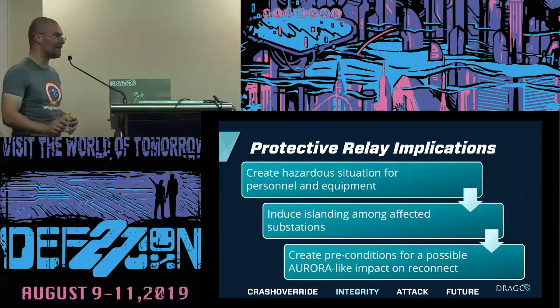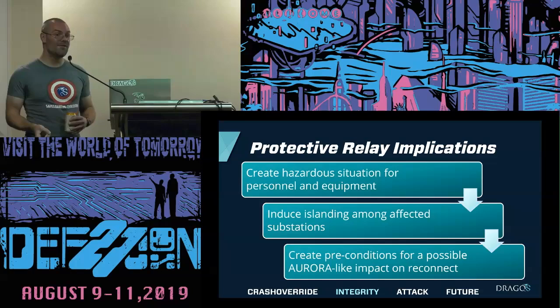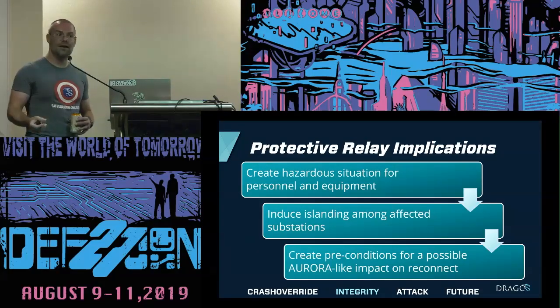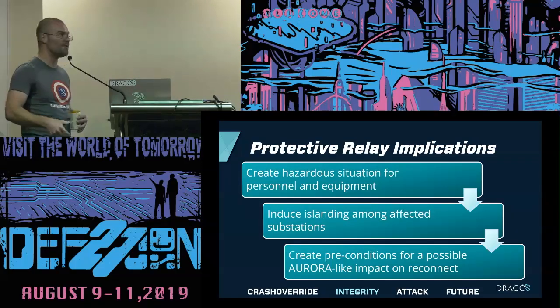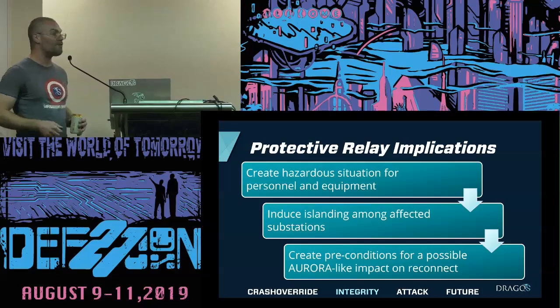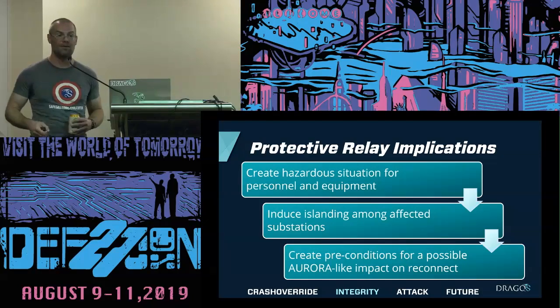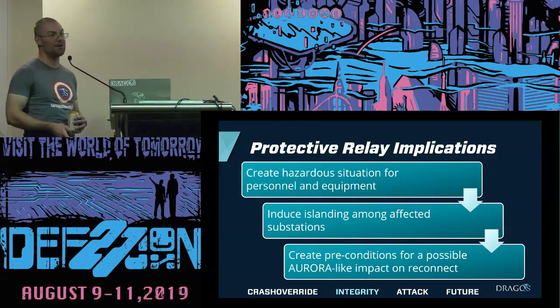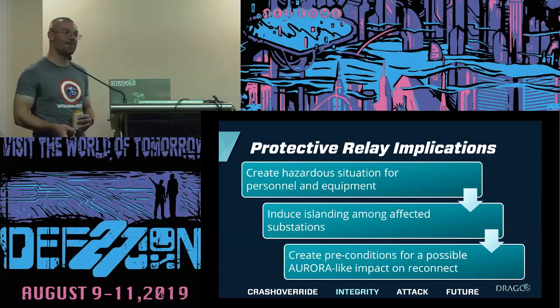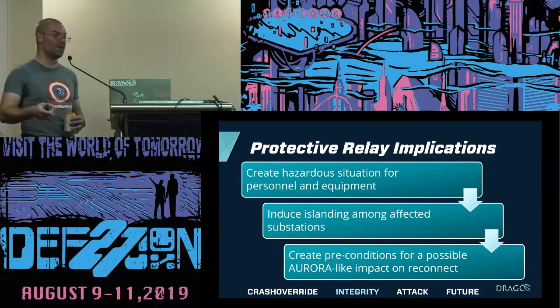So if you look at the implications of targeting protective relays as part of overall electric operations, primarily at a transmission or generation level, you can create a hazardous situation for personnel and equipment. You can burn through transformers because you got too much power flowing, or cause lines to sag because of that overcurrent situation, resulting in a fault when it hits a tree.